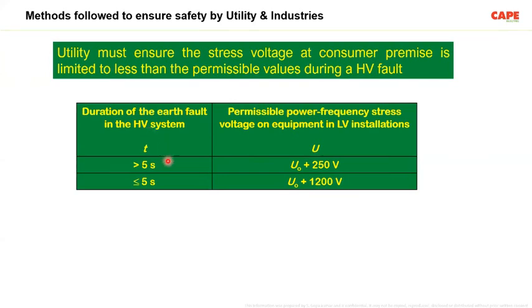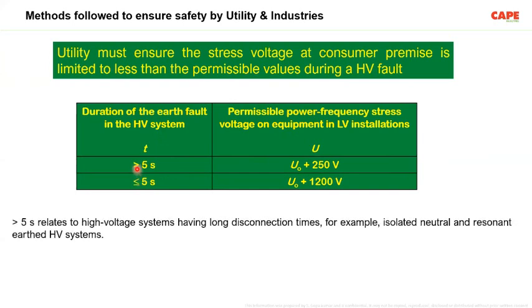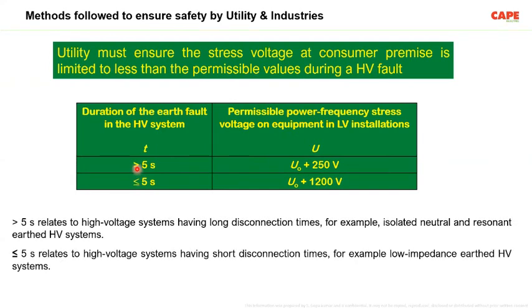For that temporary overvoltage, there are two conditions: a disconnection time greater than 5 seconds, or less than or equal to 5 seconds. Greater than 5 seconds is an indication that the 11 kV side, the high voltage feeder or the high voltage transformer, is an unearthed system. Less than or equal to 5 seconds is applicable for an earthed system. Imagine an earthed system: the 11 kV side is going to disconnect in case of a fault at a time less than or equal to 5 seconds.